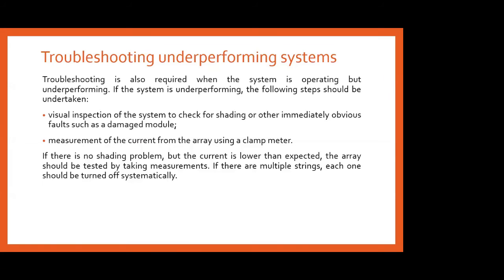Then a measurement of the current from the array, of course using a clamp meter, we can check. For the shading, if there is any problem, what are the proper measurements we have to take? And if there are multiple strings, each one should be turned off systematically for measuring. If one of the strings is not providing power, then there will be no change in the current when that string is turned off.